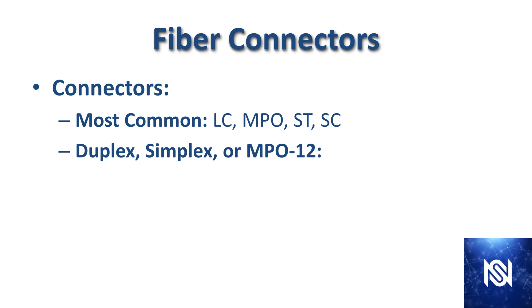Now we're going to look at fiber connectors. The most common connector types are the LC, the MPO, the ST, and the SC. These fiber cables can be either duplex, simplex, or the MPO type. Duplex is bi-directional — there are actually two channels in the cable. Simplex is just one channel, meaning you can only go in one direction at a time. The MPO type actually has 12 individual wires, and it is a very different type of fiber cable than the others you'll see most commonly.